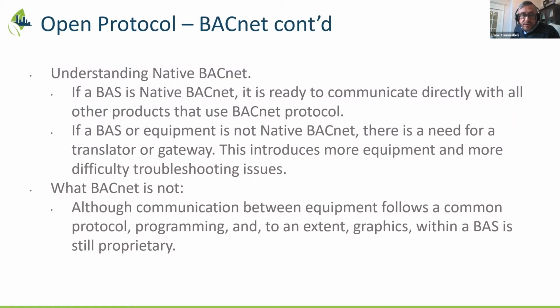If a BAS or equipment is not native BACnet, there's a need for a translator or gateway. Nothing is wrong with that, but one should be mindful that it introduces more equipment into the equation, making it a bit more challenging to troubleshoot. That's why we want to highlight this.